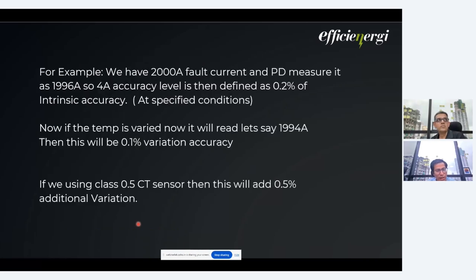For example, let me explain what intrinsic accuracy is. Suppose we have a fault of 2000 ampere and the protection device measures it as 1996 ampere. The 4 ampere difference is the accuracy level defined as intrinsic accuracy, and that comes out to be 0.2 percent. Then there is a second test to be carried out by the manufacturer, where the conditions are specified as per the standard, but now a variation is brought into the ambient temperature, and again the test is carried out. At this time, the protection device reads the fault current as 1994 ampere. Again, a lesser quantity is measured. This is basically a 0.1% variation, based on 1996 ampere.